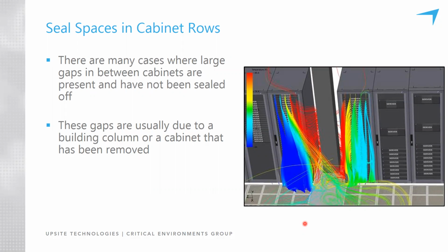which is openings in the rows of cabinets. And this CFD analysis of conditions before, with the area open, shows the hot exhaust air circulating through those spaces and causing elevated temperatures along the edges of the cabinets. Not the entire server. The server, if there are inlets across the full face of the server, farthest from the gap is getting nice cold air, but right next to the gap is getting very hot air. So it's important to consider intake temperatures at a really granular level, because sometimes monitoring or even sensors within the equipment can miss these high intake temperatures in very isolated locations.